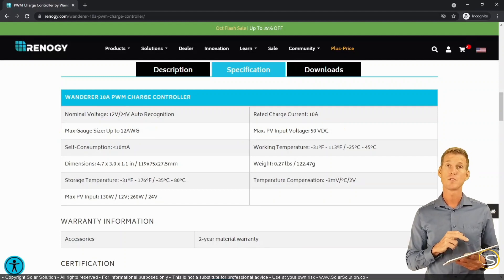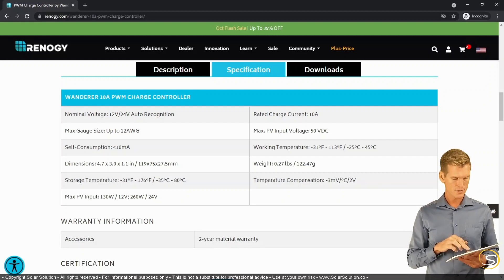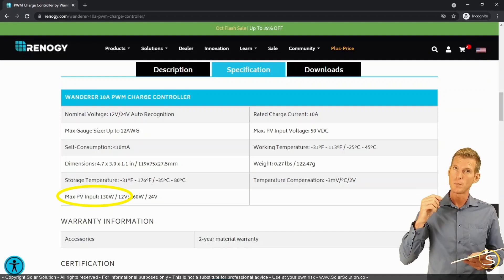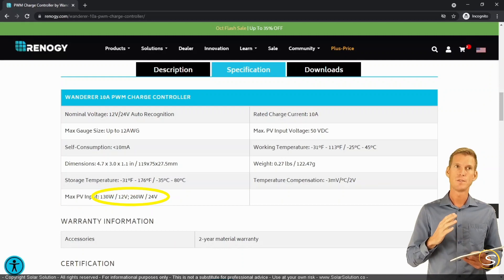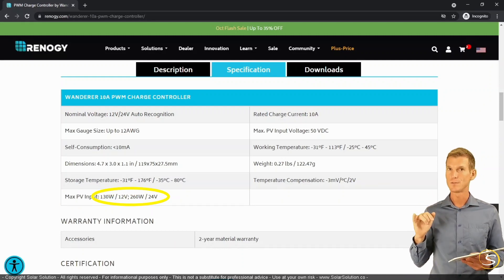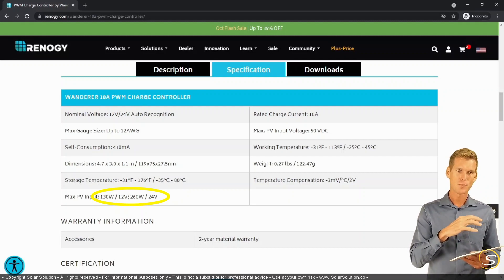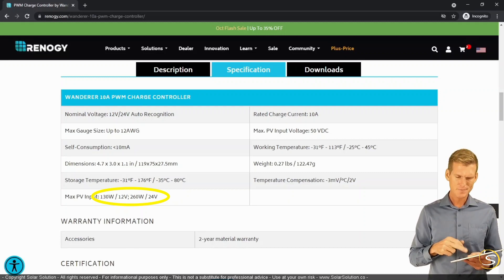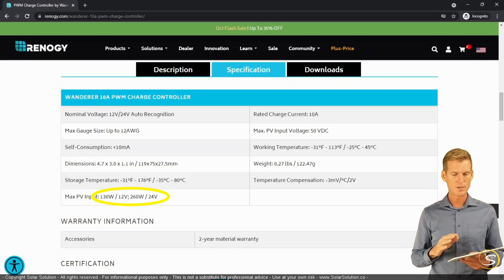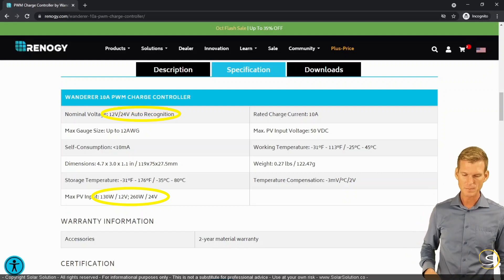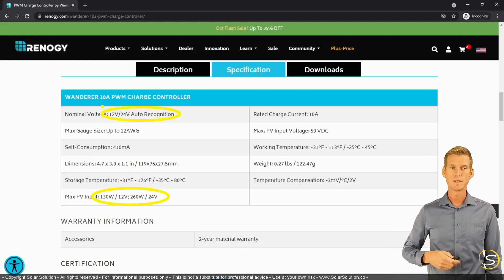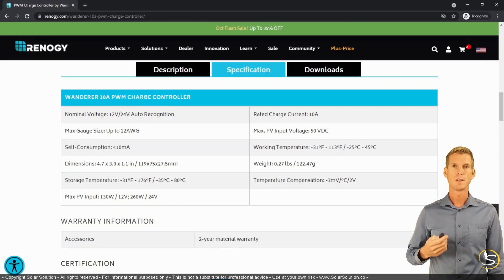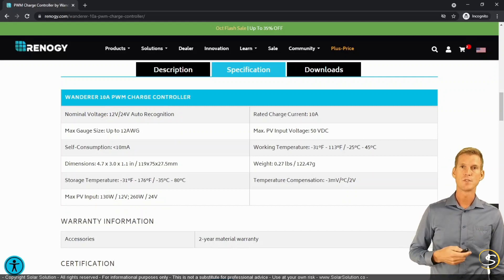Here we can see the maximum amount of solar power you can connect to this charge controller: 130 watts for a 12 volt system, and double that if you're operating a 24 volt battery bank. So this is a real advantage — using the very same charge controller but with a higher battery bank voltage allows you to connect much more solar power while still buying just one charge controller. Depending on your situation and your flexibility in choosing a battery voltage, this can be a real advantage. So now you understand a little bit how a PWM charge controller works.